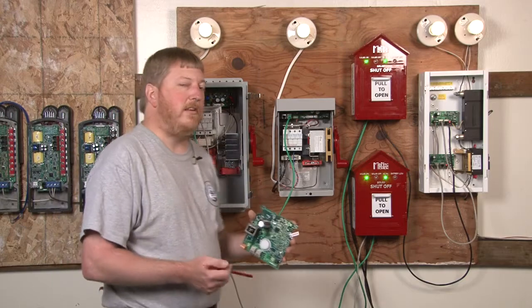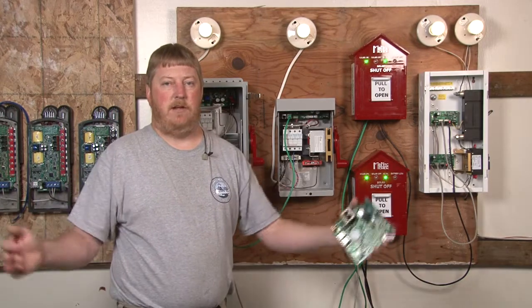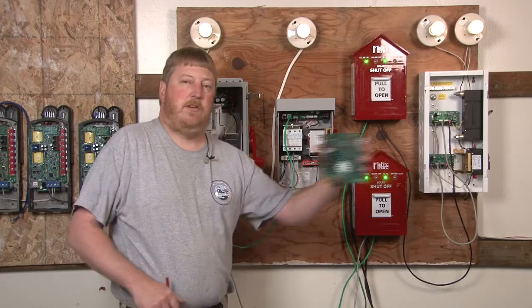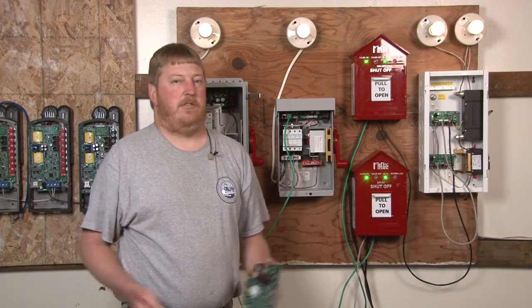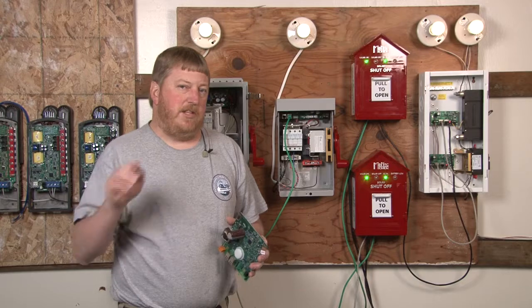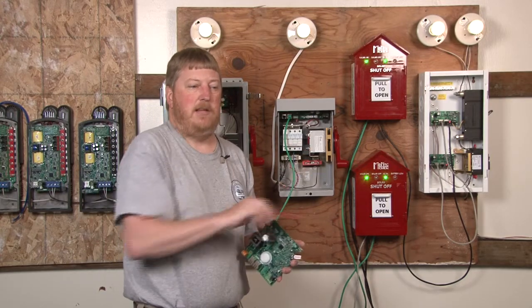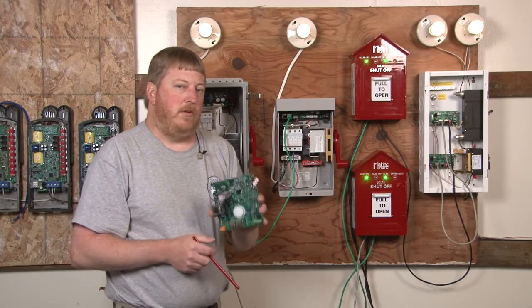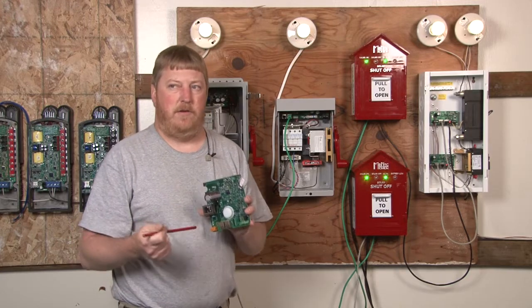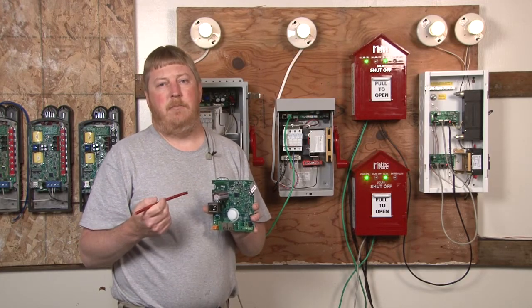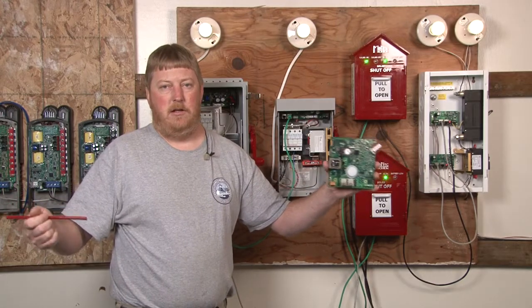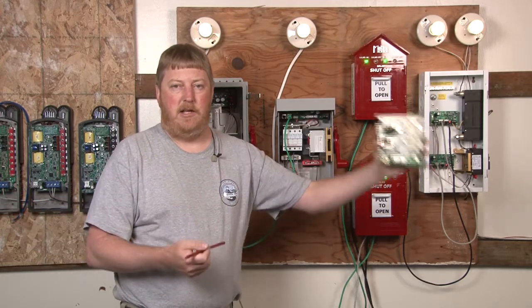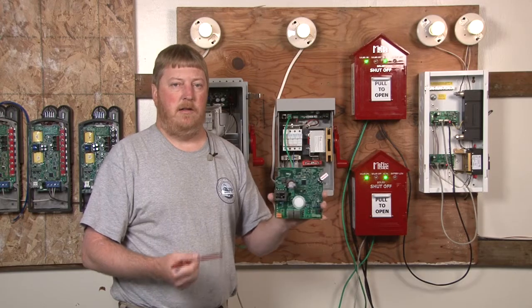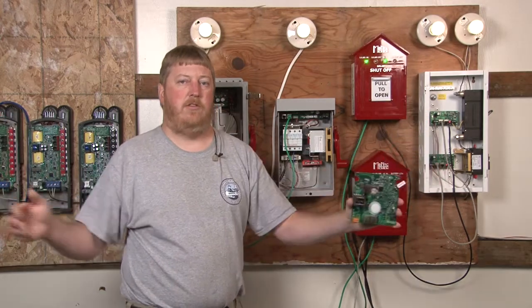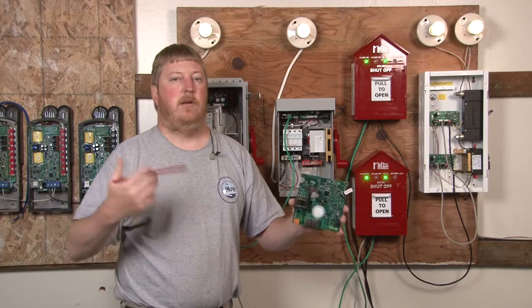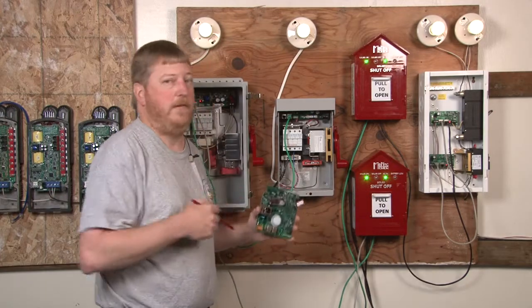So what that means basically is you can have, say 100 devices. You could have 40 combiner boxes, 50 or 60 battery disconnect modules, and 6 or 7 birdhouses. And they daisy chain one to the other, to the other, to the other end. I do want to point out that due to the way the birdhouse works and its fail-safe circuitry, the birdhouse cannot be on both ends of that string. They have to be all together in a line. They can be on either end, or they can be in the middle somewhere, but you can't have birdhouses on both ends, otherwise you'll get a fail-safe signal from both ends, which will cause the system to not turn off if a cable is damaged.